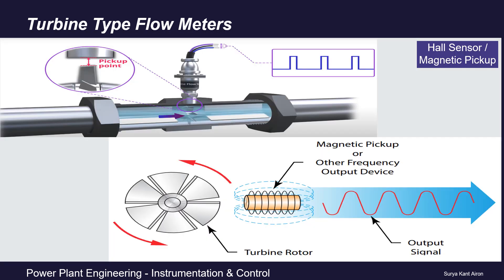If a Hall sensor is used — Hall sensors are basically magnetic pickups — the spacing between the rotor and the magnetic pickup varies during rotation due to the gap between the blades. This magnetic pickup generates a magnetic field. As the rotor rotates on its axis, this magnetic field is cut, and the sensor detects the change in the magnetic field and sends this signal to the transmitter.